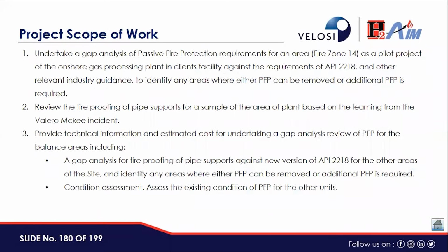The scope of this case study was to undertake a gap analysis of PFP requirements for an area, which was fire zone 14, as a pilot project of the onshore gas processing plant in client's facility against the requirements of API 2218 and other relevant industry guidance. The scope of work includes identifying any areas where either PFP can be removed or additional PFP is required.